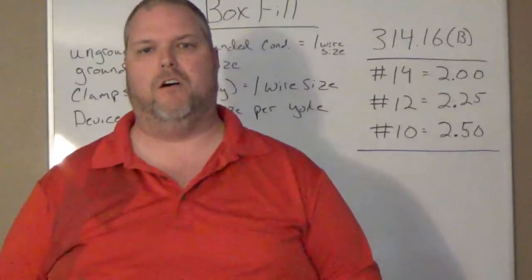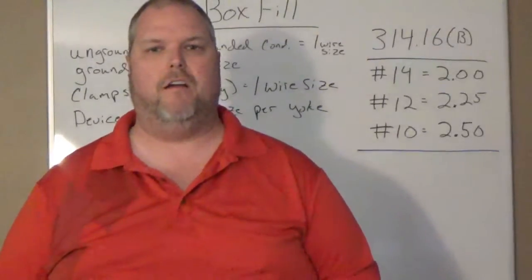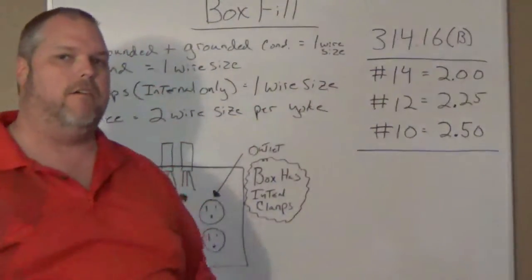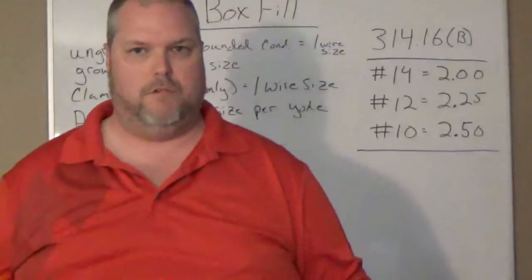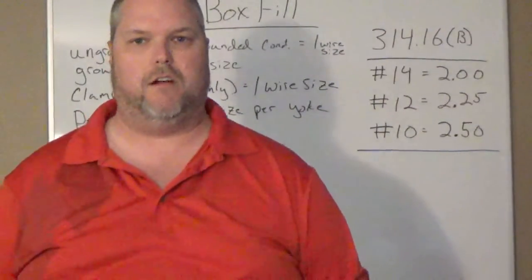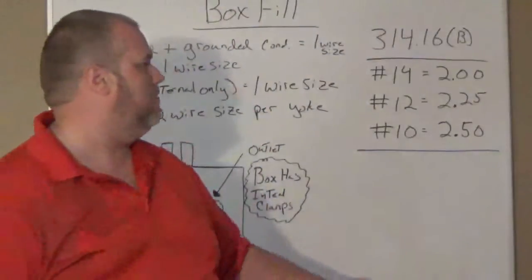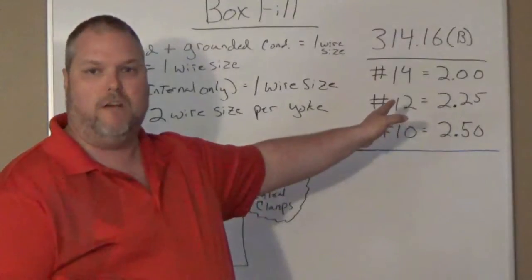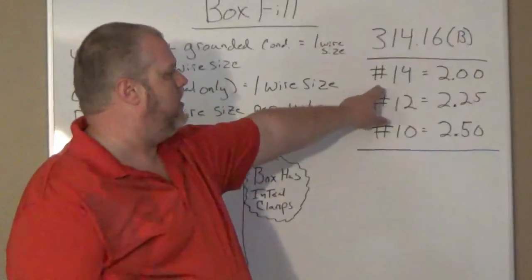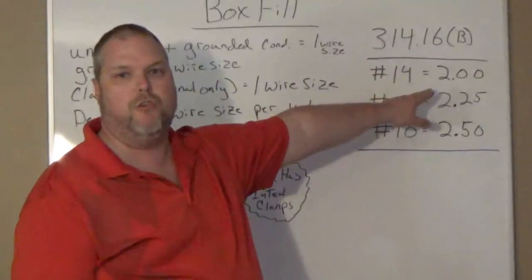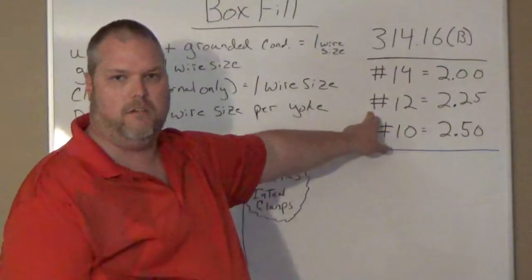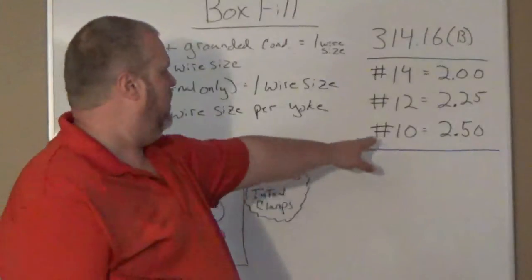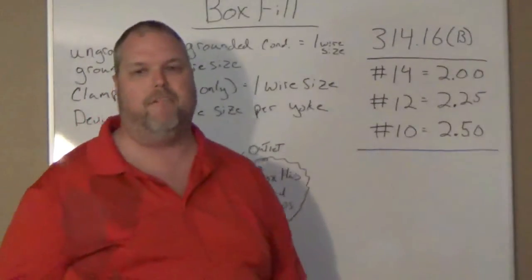Something that we need to understand, we need to understand that in article 314.16(B), that's going to give us our volume for conductors, one single conductor. So it basically states something like this: If you looked in the NEC codebook and we're talking about the 2014 codebook, 14 is equal to 2 cubic inches. A number 12 conductor is worth 2.25 and a number 10 is worth 2.5.